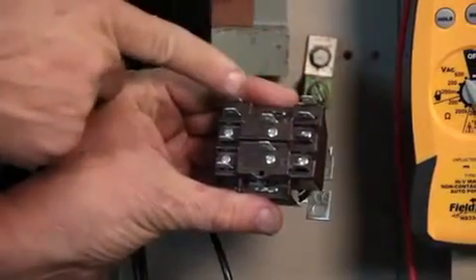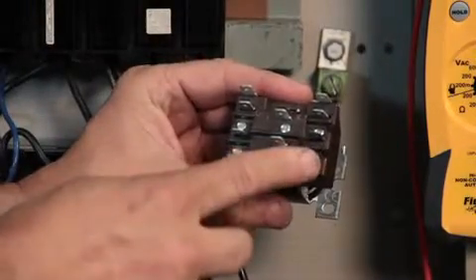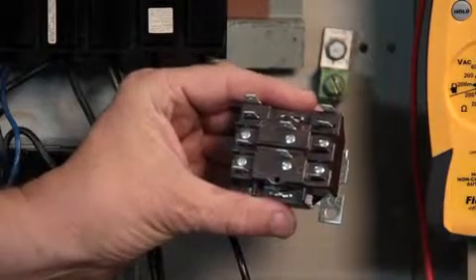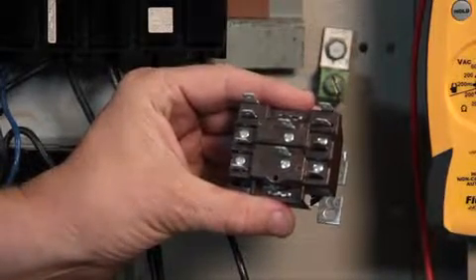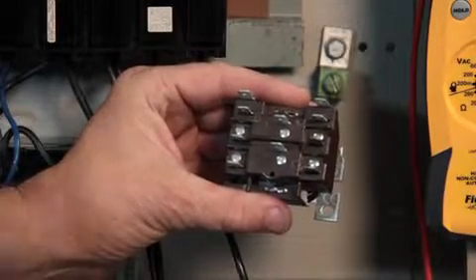We have our 24 volt power coming to the coils. Then we have the sets of contacts where we have a normally open set of contacts and a normally closed set of contacts. We're going to check with our voltmeter, make sure we have voltage coming to the contacts. When they close, we should see that power pass through it.